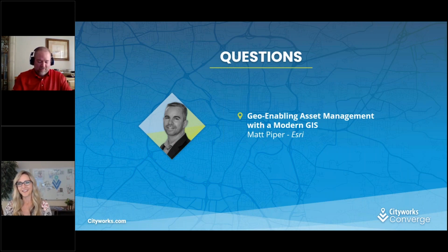Here's a question for you: where is the relationship between SCADA and GIS made? It's actually made through the API. The relationship exists because we have the asset ID on the SCADA tag, and the assets exist in a non-spatial table in the GIS. What brings them together is the API that pushes that data from the SCADA tag to the Cityworks API and creates the work order. So without the connection at the SCADA tag level you couldn't do it, but the API is what really makes the handshake.